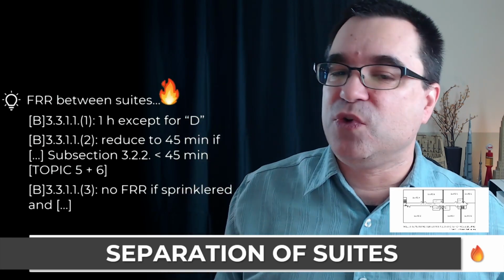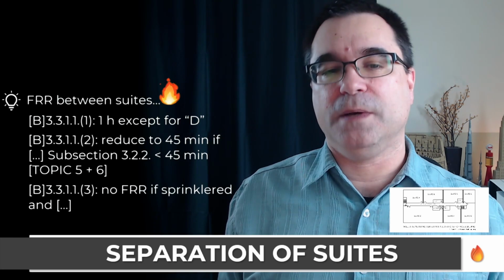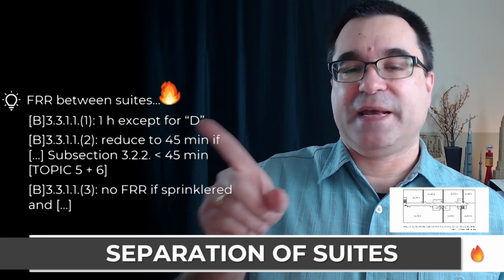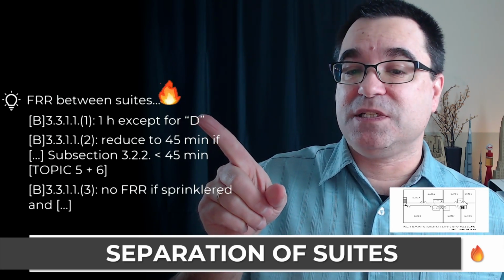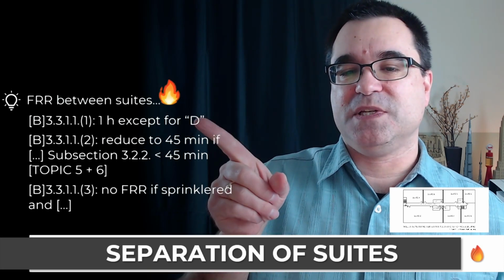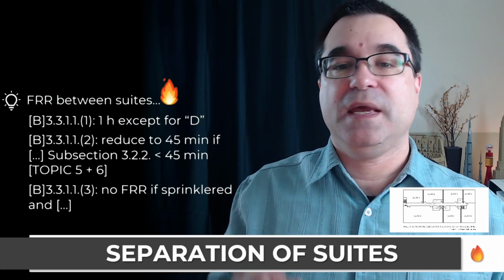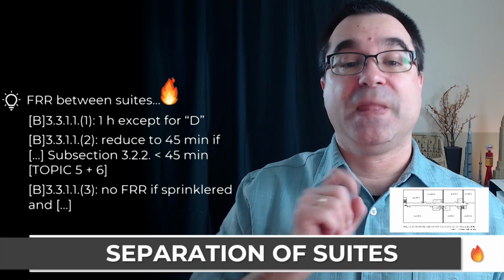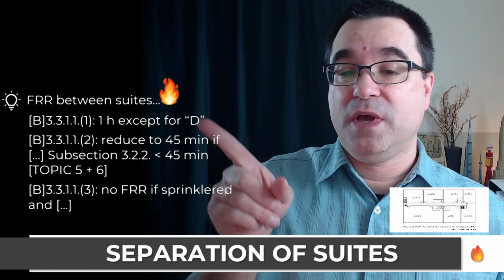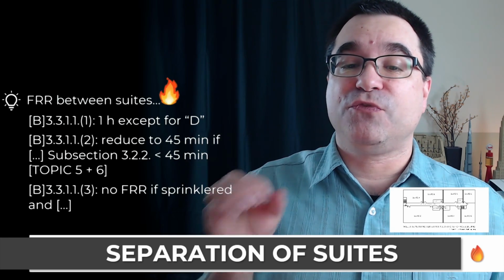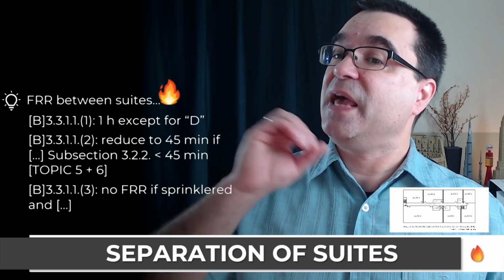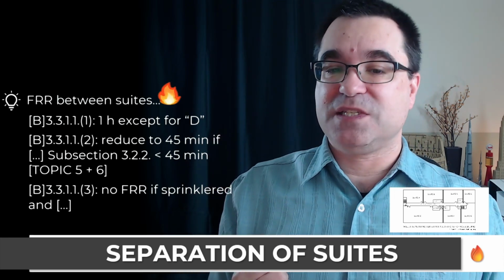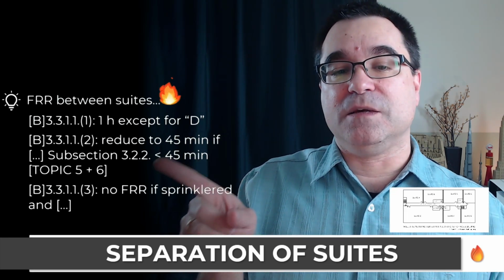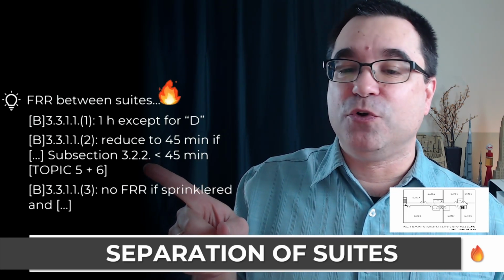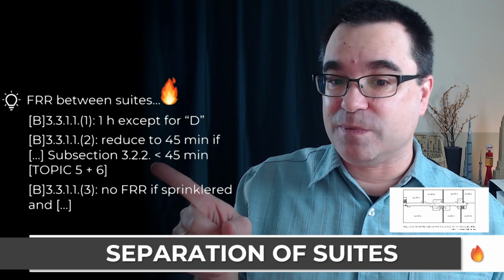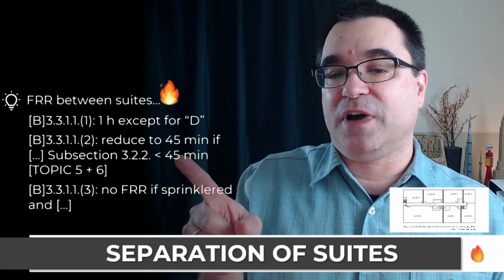According to sentence 3.3.1.1.(1), except for D major occupancies, okay, so this is business and personal services, it's 1 hour. According to sentence 2, this 1 hour can be reduced to 45 minutes if the fire resistance rating that you get for other items under subsection 3.2.2 for that major occupancy is less than 45 minutes.